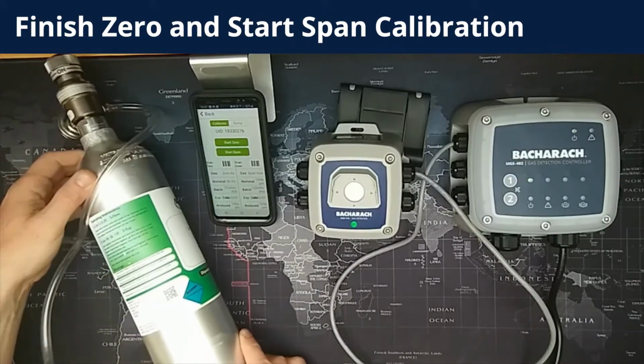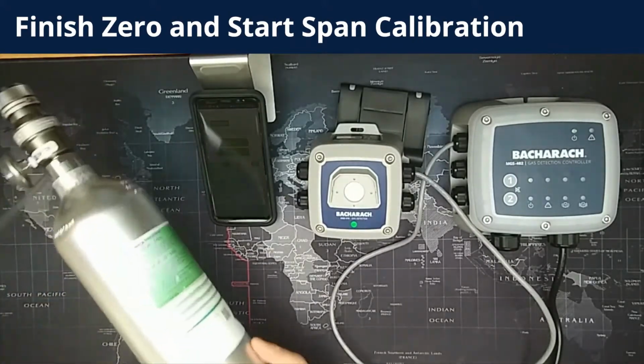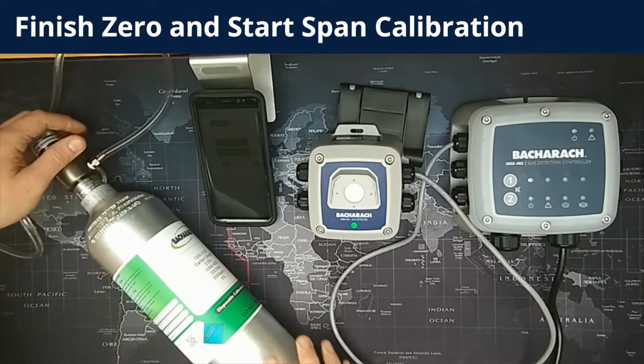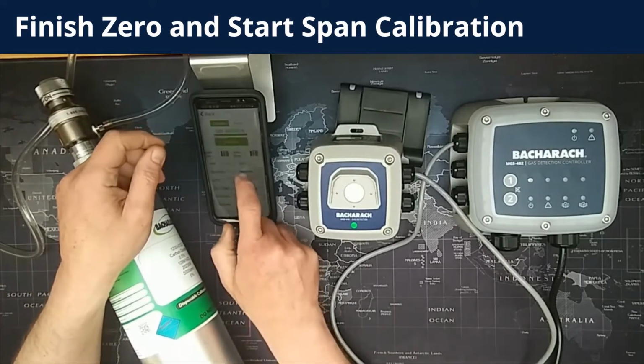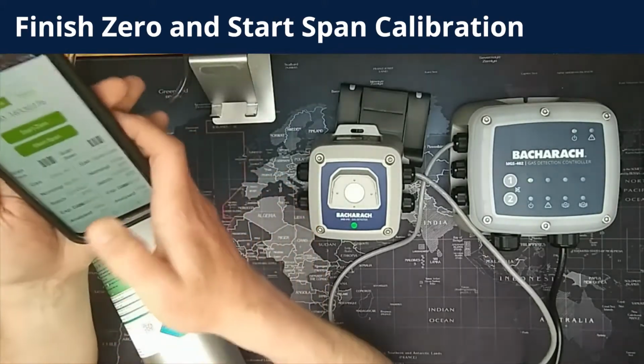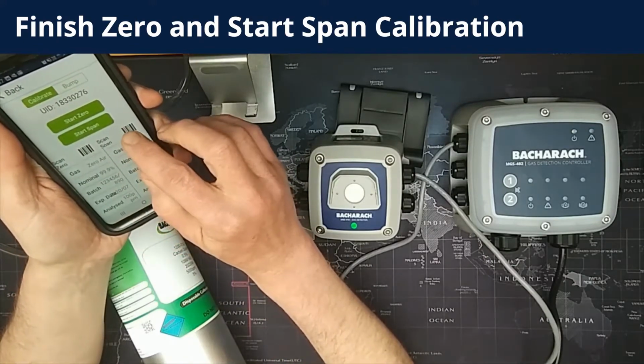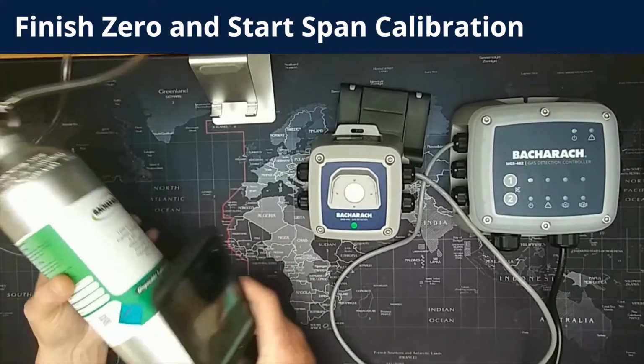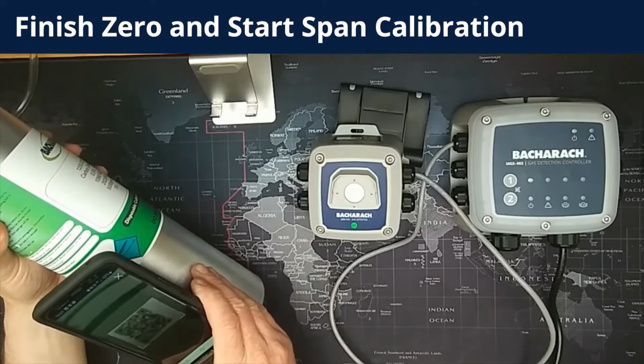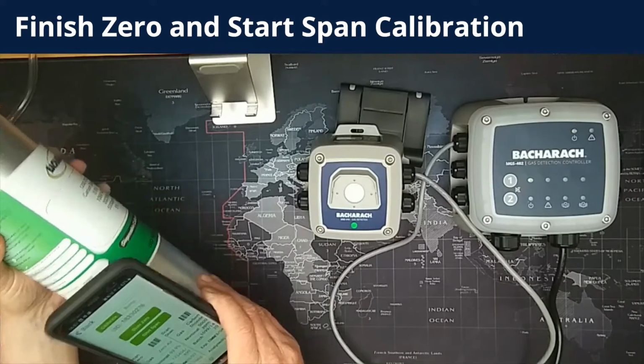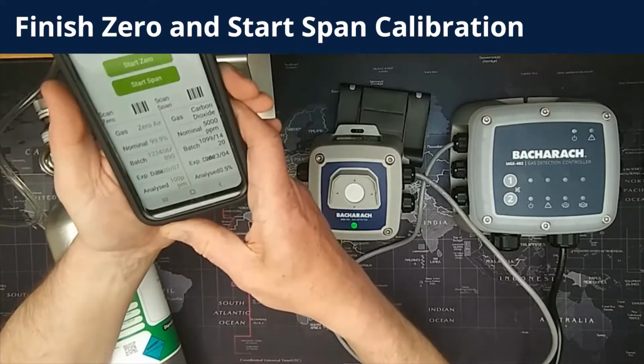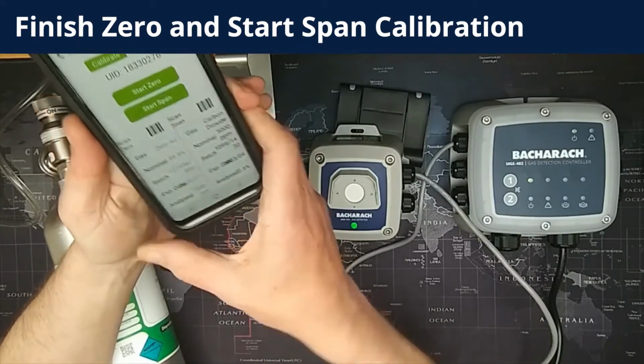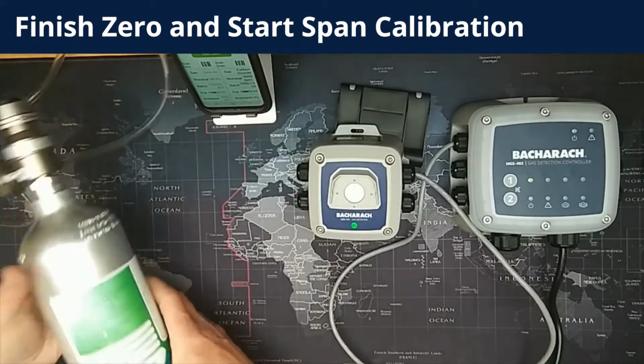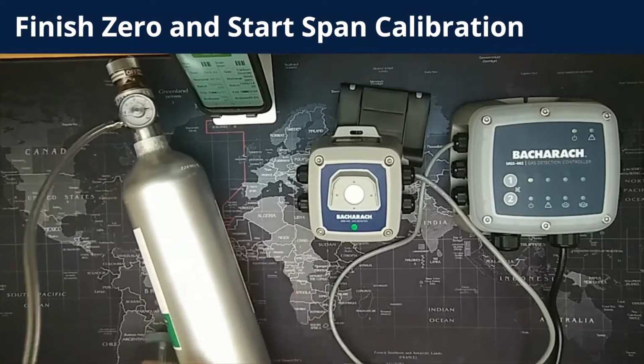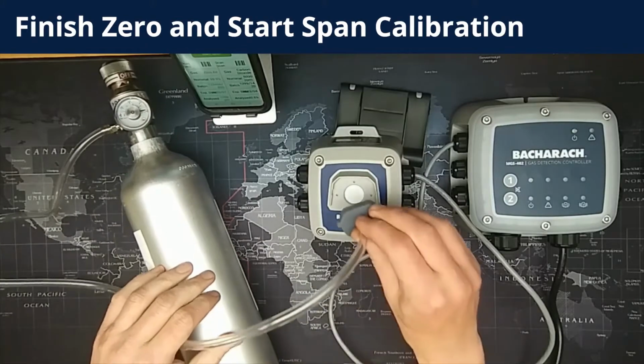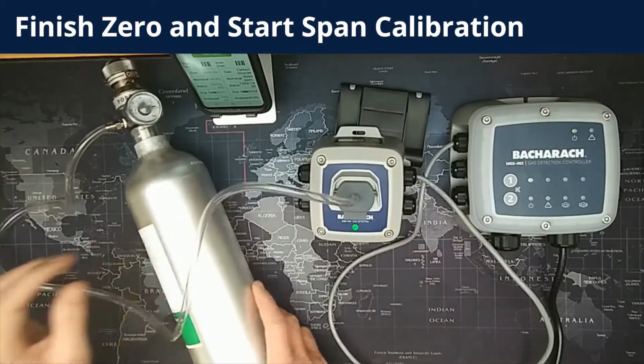You now need to enter those details into the app. And the way to do that is exactly the same way. You're looking for the QR code on the side of the cylinder. And you're going to select the scan span. That's it right there. It'll open up the camera and allow you to scan that code on the side of the cylinder, and that will enter all of the details of the span gas into the calibration screen, and that is then used for the production of the PDF calibration certificates at the end of the calibration process.